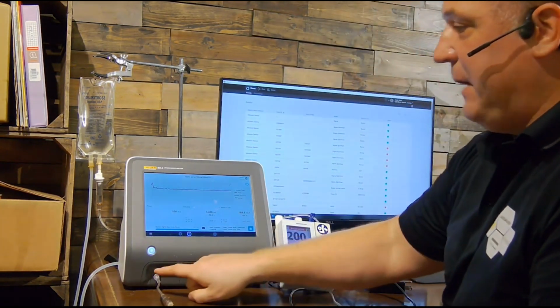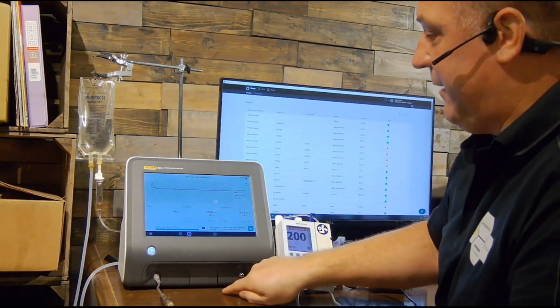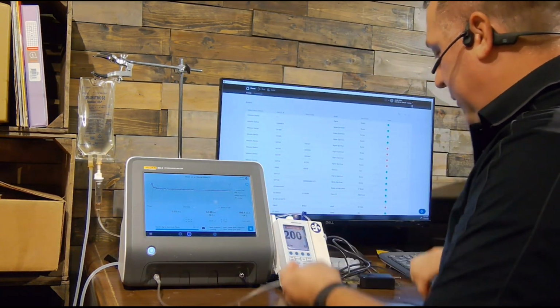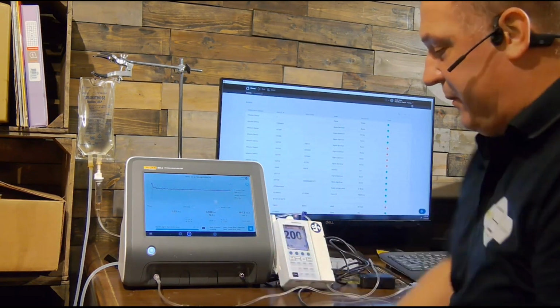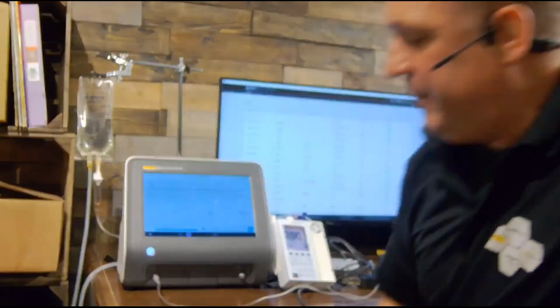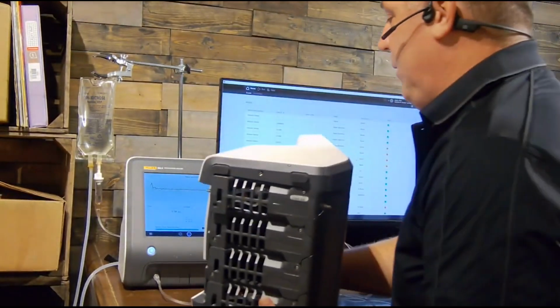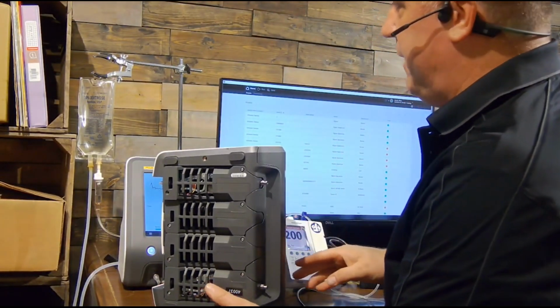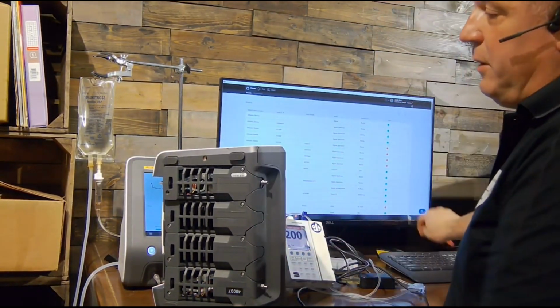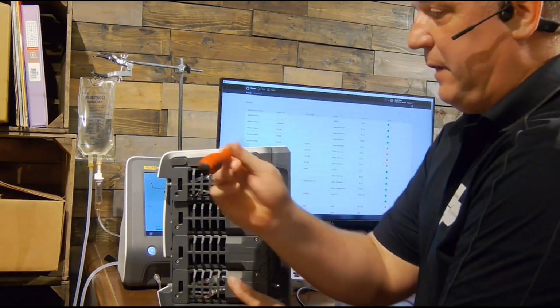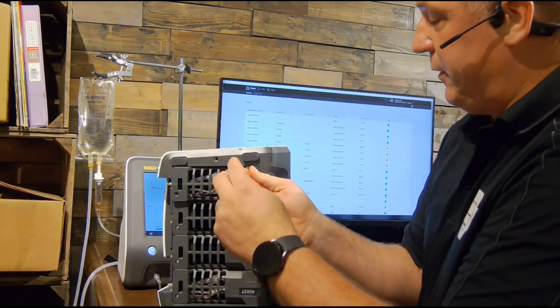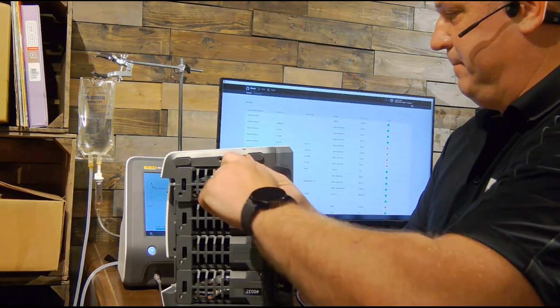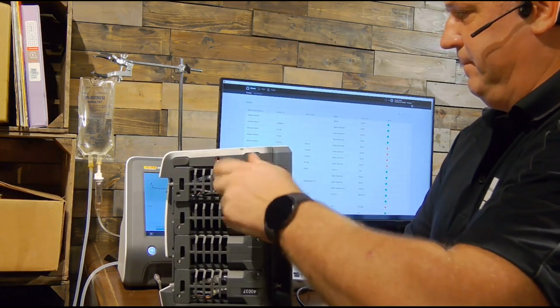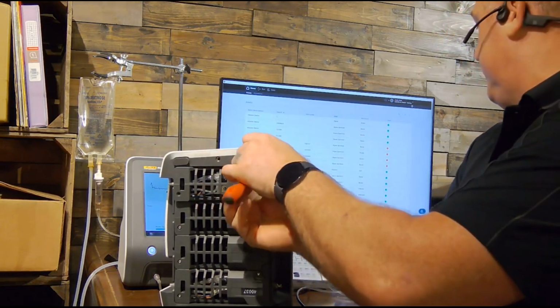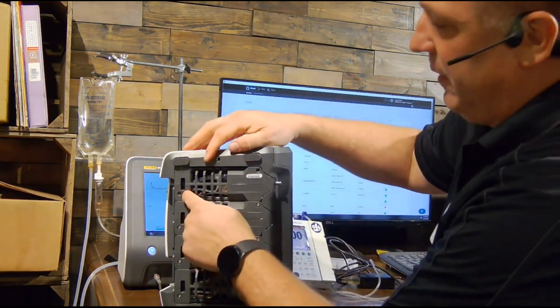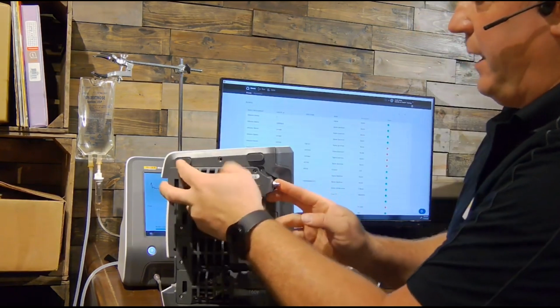IDA-6. So I mentioned that this is a 2-channel version. It can accept up to 4 channels. So let's go ahead, and I want to talk to you about this because this is awesome. When it's time to send in the IDA-6 for calibration, I don't have to send in my entire IDA-6. So I happen to have another IDA-6 here. And the only thing I have to do is take out the channel. So it takes a T10 screwdriver. I take out 2 screws. This one, and I already took the other screw out earlier. The one over here. And then this channel will slide right out.